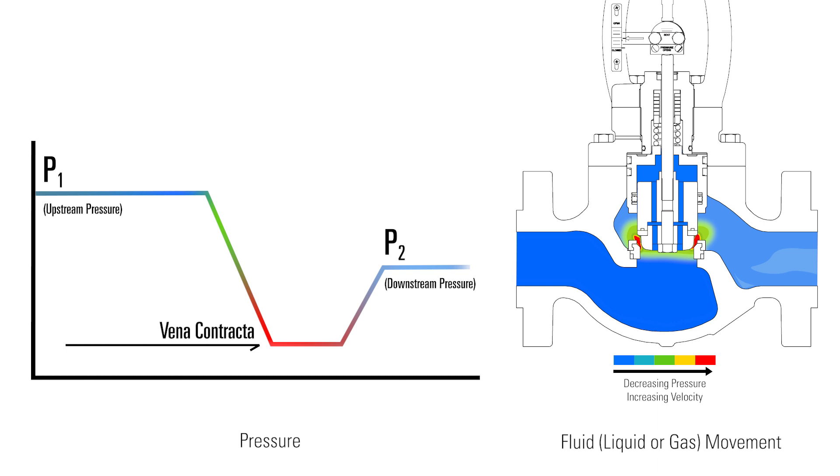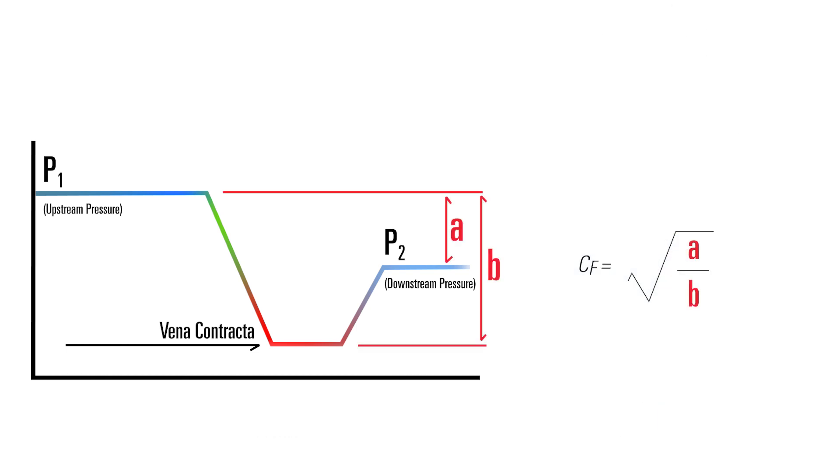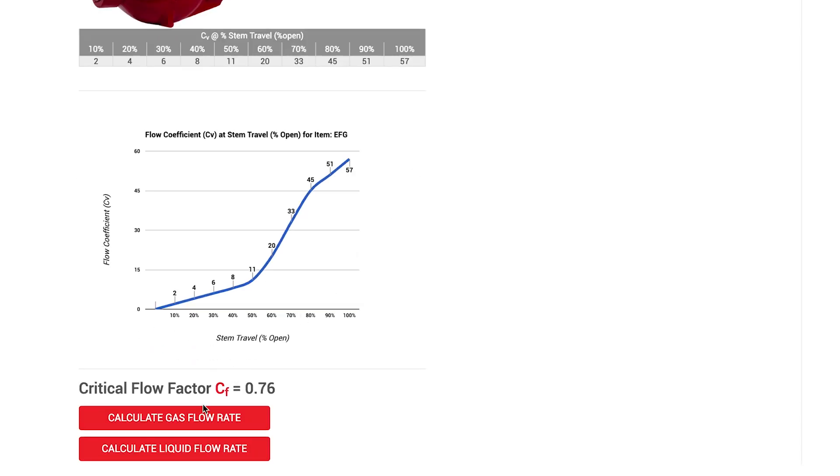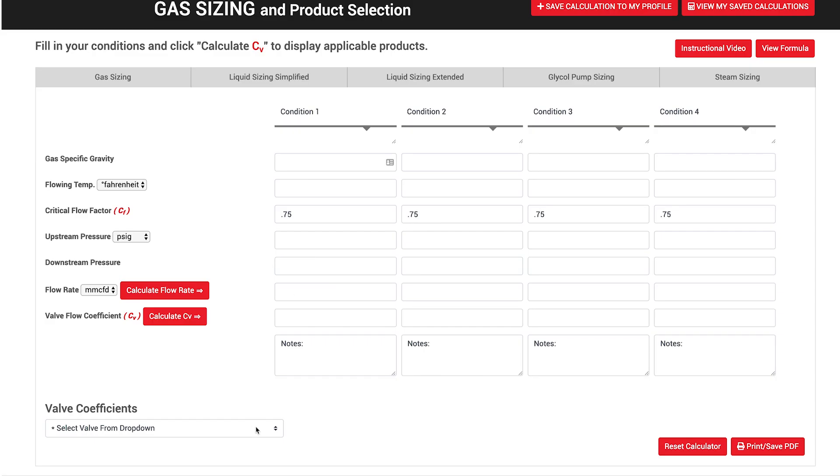Kimray calculates the critical flow factor based on this pressure recovery, using the formula shown here. You can find the CF for each valve on the product detail page or on the sizing page under the valve coefficients drop-down menu.